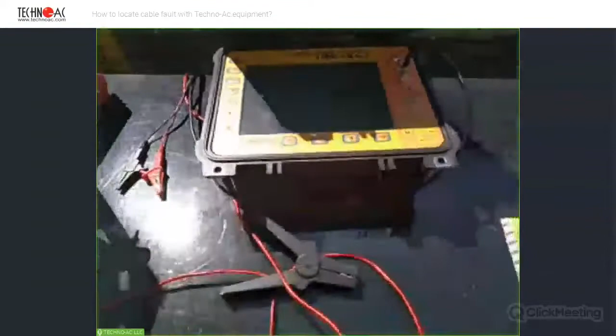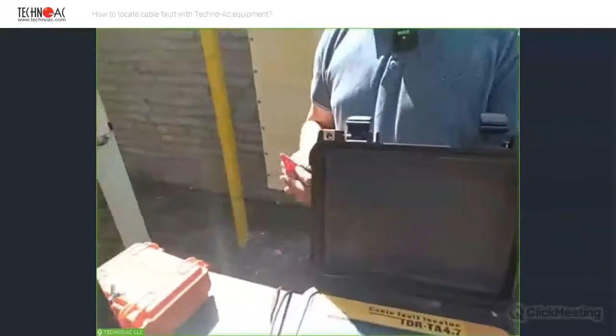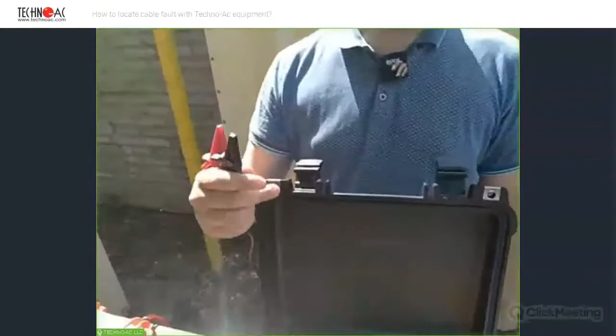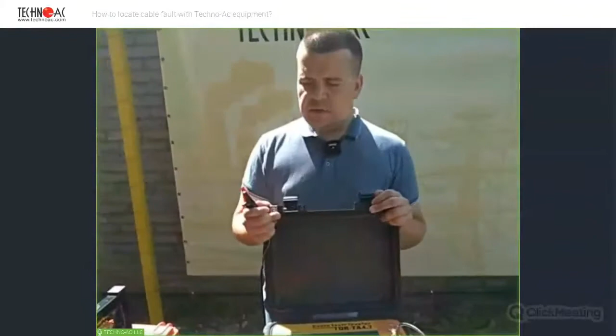As this device is mostly used for power cables, you have to observe safety precautions before using it. First of all, you have to discharge your cable, and then use a megohmmeter to test the resistance of the fault currently affecting the cable. When you have done all the precautions, you connect the crocodile clamps to the leads, the rods or conductors of your cable. Usually you do this on your substation or in a junction box, but today we're going to locate the faults in our test cable. So I'm removing the safety cap here. Of course, this cable is completely discharged and it doesn't carry any current or voltage, as far as I know.